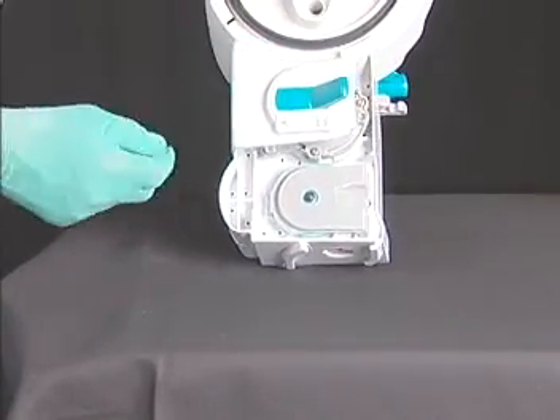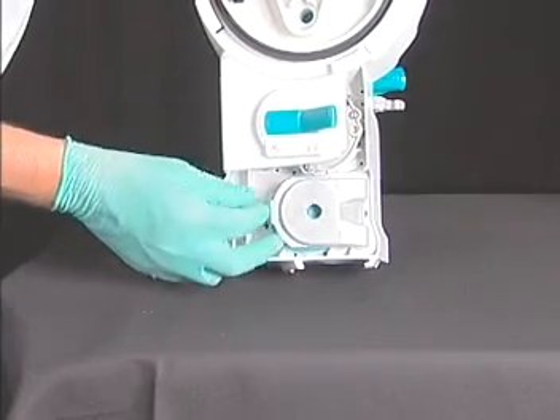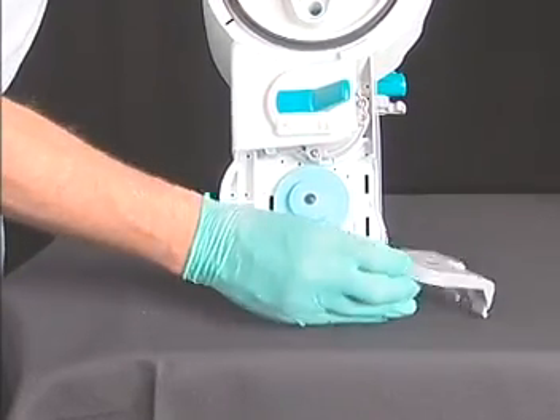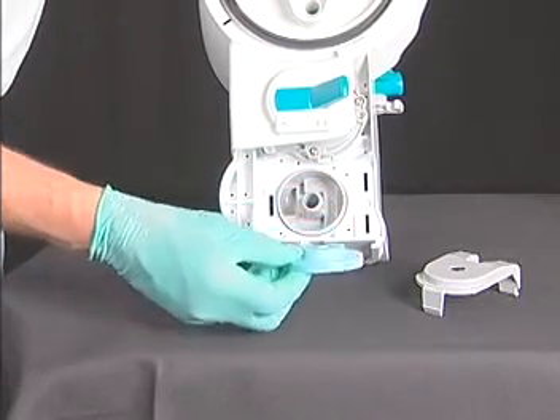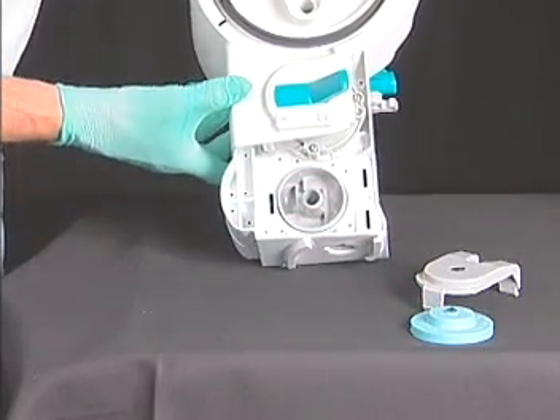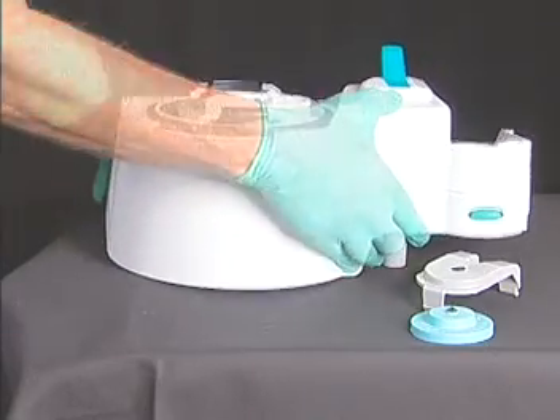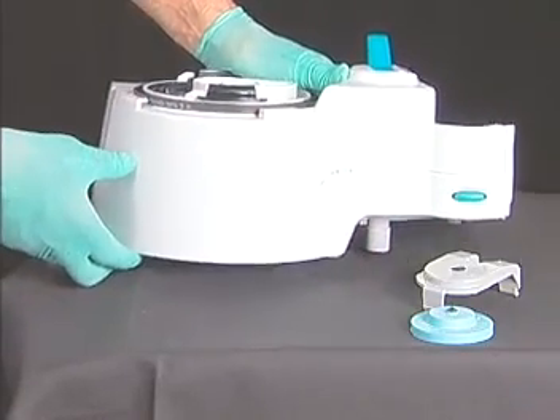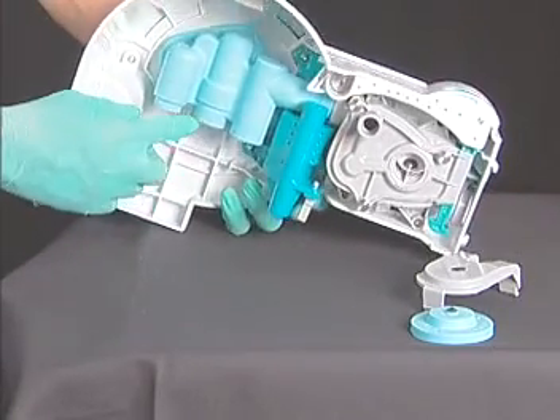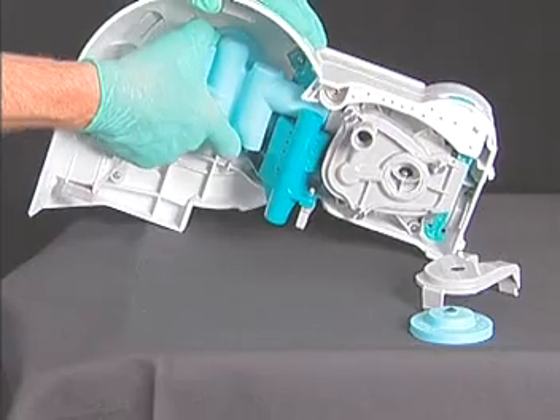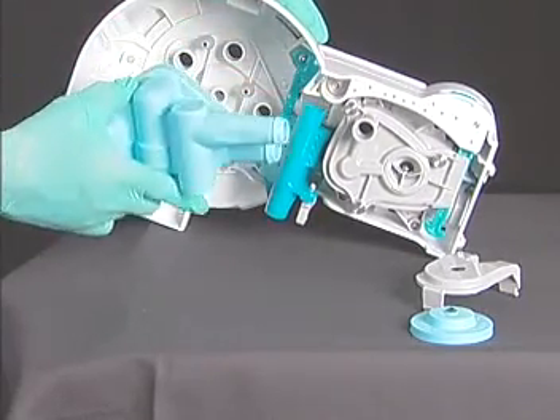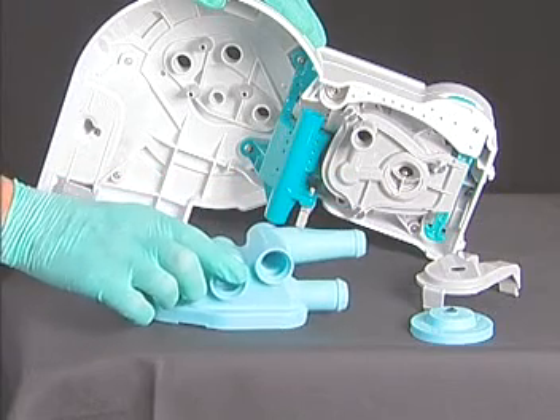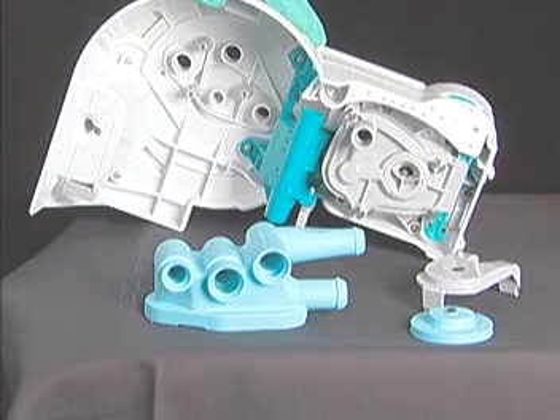The APL ramp can be removed by putting slight pressure on the tab connections as shown. Removal of this component provides additional access to the interior of the bellows base assembly. Turning the bellows base assembly upside down reveals the boot. This component is easily removed by grasping it and pulling it away from the bellows base. Disassembly to this level provides excellent cleaning access to all components of the ABS which come in contact with patient gases. Any additional disassembly of the ABS should only be done by a qualified service technician.